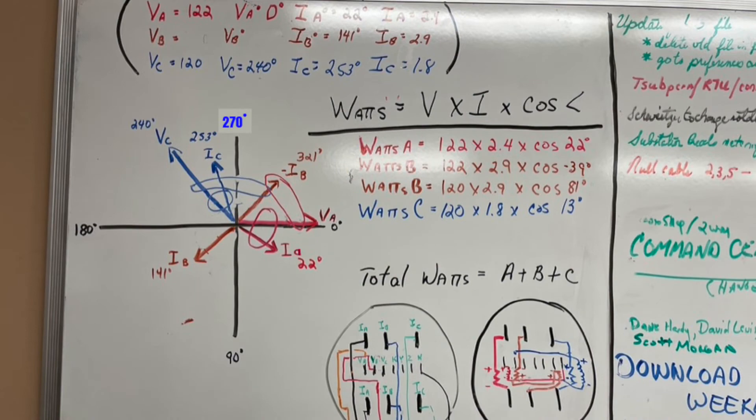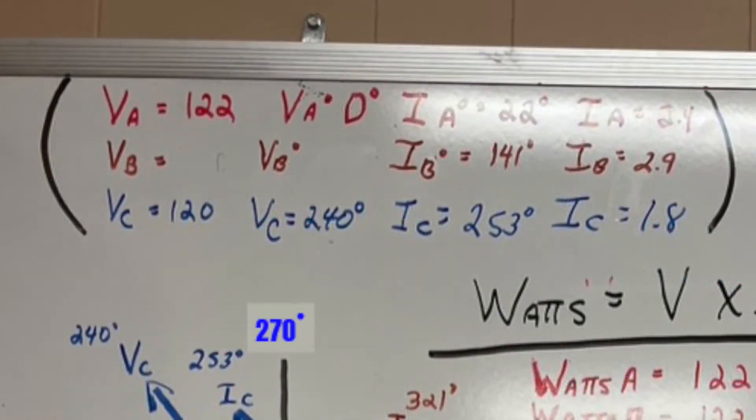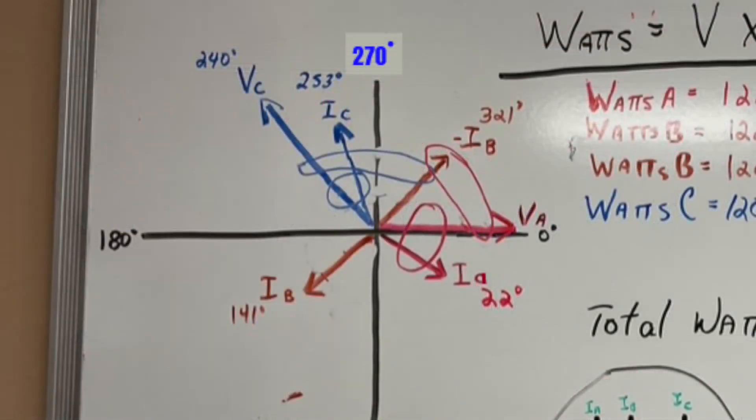This is a Form 6 meter and as you can see in the given values, we no longer have a voltage B value or a voltage B angle. We're going to go ahead and plot these given values on the chart and we will have voltage A at zero degrees, current A at 22 degrees, we have current B at 141 degrees, and we have voltage C at 240 degrees and current C at 253 degrees.